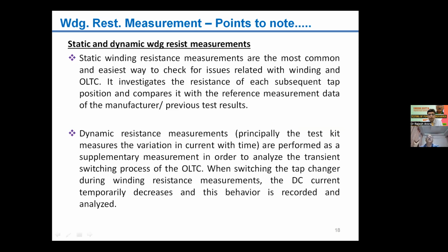Generally two types of winding resistance measurements are done nowadays: static and dynamic. Static measurement means you measure the winding resistance without any movement, and it is the most commonly done, easiest way to check issues related to the winding and OLTC. It investigates the resistance of each subsequent tap position and compares it with the reference measurement data, meaning the data provided by the manufacturer and the test performed at the factory level itself, and also with the previous test results.